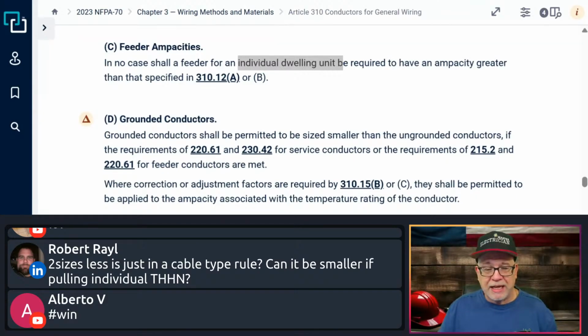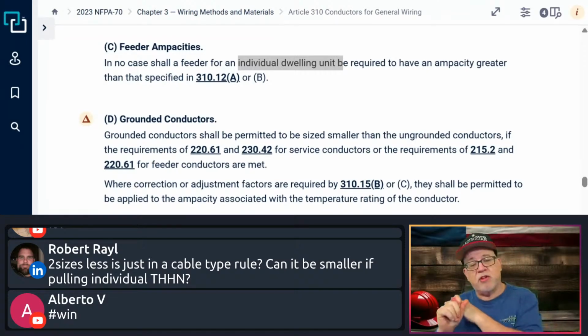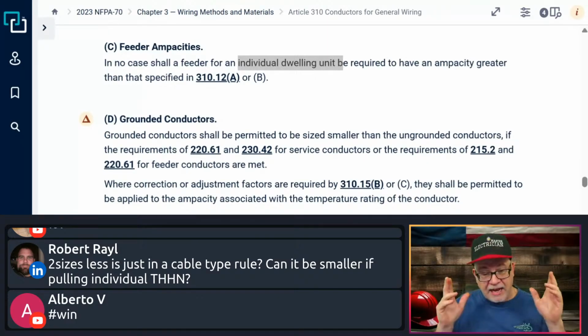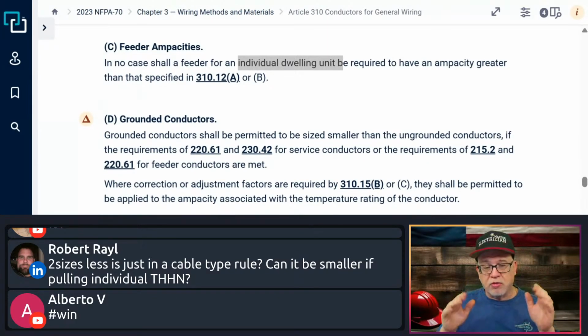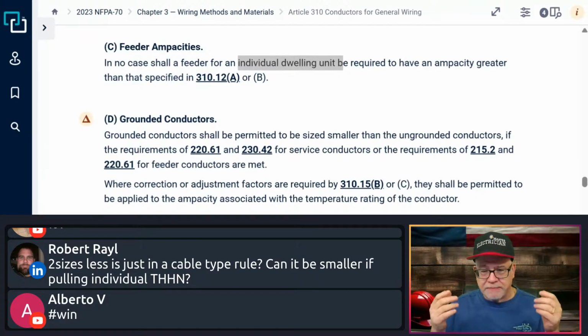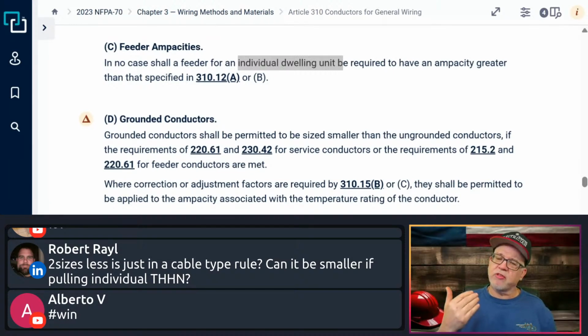As far as what you pull in a raceway, you pull whatever you want as long as it's designed to handle the calculated load and you're meeting the minimum sizes. Like for neutral, you've got to meet 250.24, which ultimately is going to send you to 250.102(C). And as long as that's not less than that, and taking into account your neutral loads and your allowances in 220.61, as long as you take all that into consideration, yeah, your neutral could be smaller than 2 sizes than your ungrounded hot conductors, yes. But just not in a cable assembly like an SE cable because it's pre-made for you. And as a manufacturer of cable, we have to follow certain rules, that type of thing, okay?